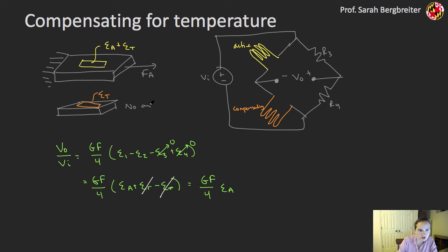So in this case, I've used an extra strain gauge that is actually not measuring any axial strain, and I've co-located that, meaning I place it close to my strain gauge that's actually undergoing the strain that I want to measure. And using that, I'm able to compensate for any temperature changes that both of those see. Now the co-location is important because if I have one of my strain gauges in one place, another strain gauge way over here, and I have temperature variations between those two locations, right, this no longer works. So I need these things located very close to each other.